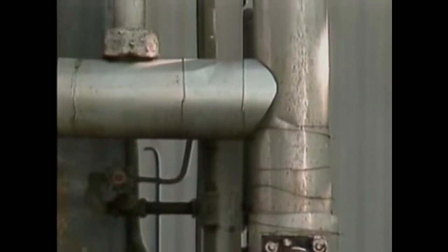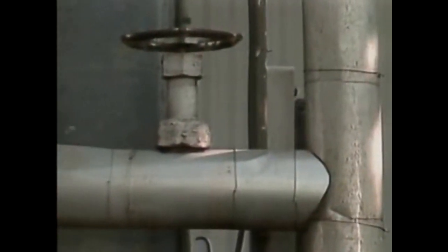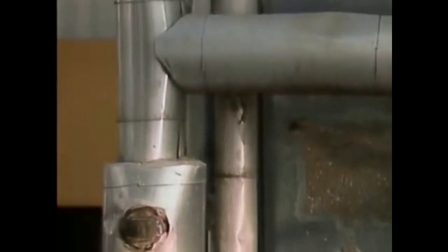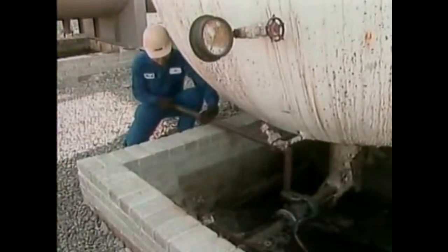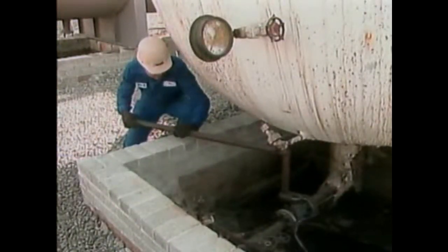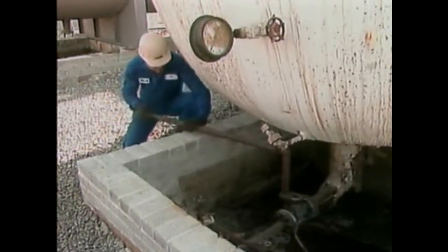A problem that may occur in gas systems is freeze-ups in the fuel lines. In cold weather, condensation in the fuel can freeze and create problems for the operator. A knockout drum can remove most of the condensation, but a small amount may remain in the fuel that's sent to the furnace. In cold weather, even a small amount can cause a freeze-up.